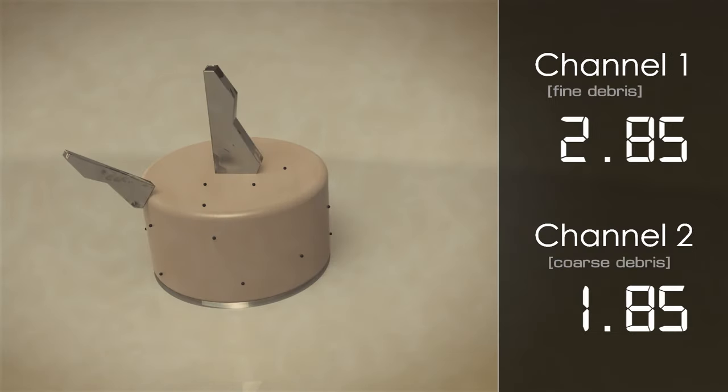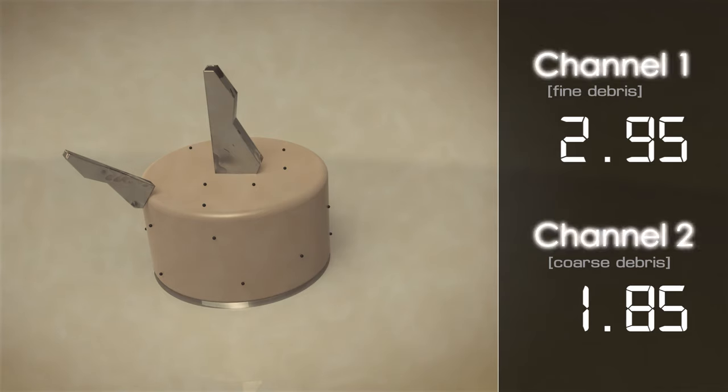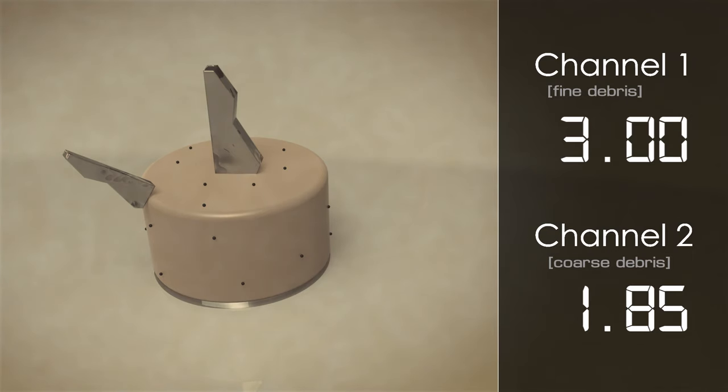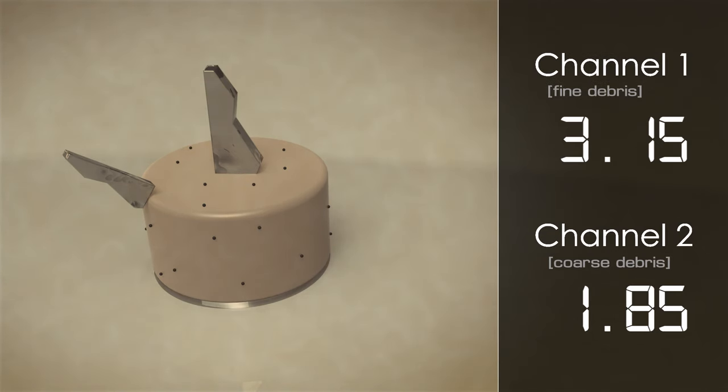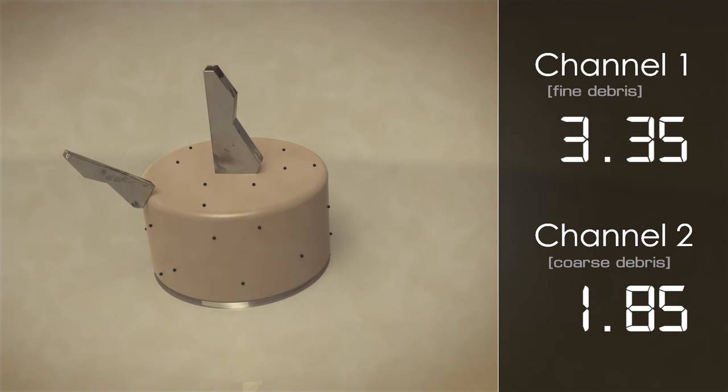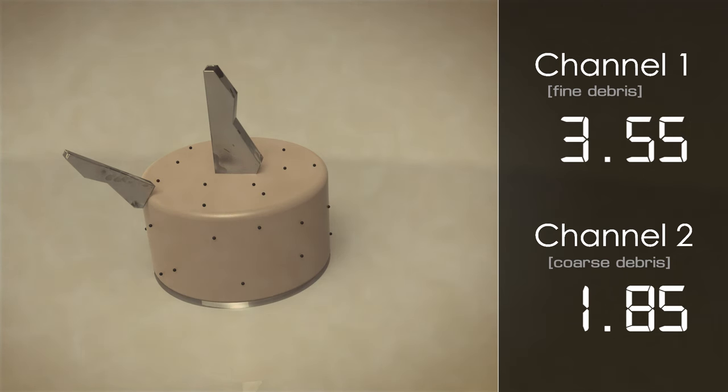The sensor has two independent analogue output channels. The first channel, referred to as the fine channel, is configured to measure the build-up of fine metallic debris, typical of normal engine or transmission wear.